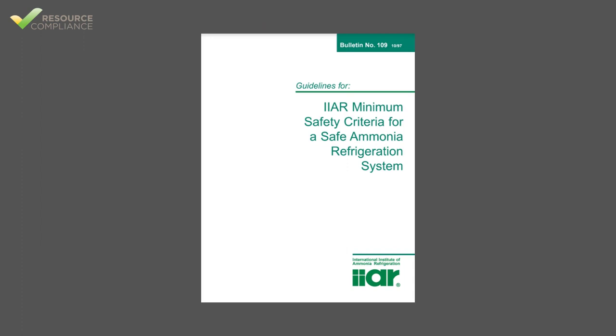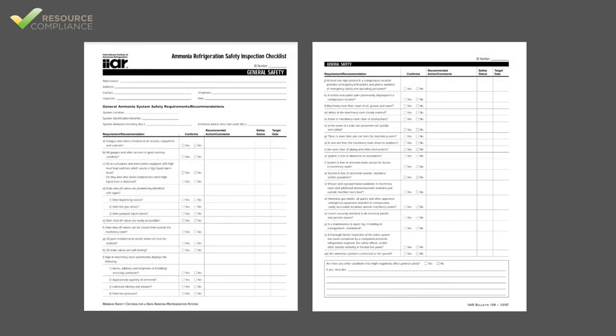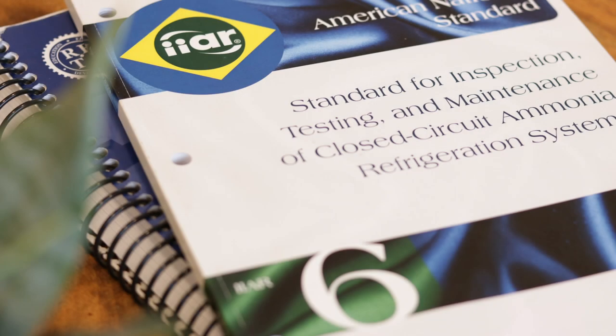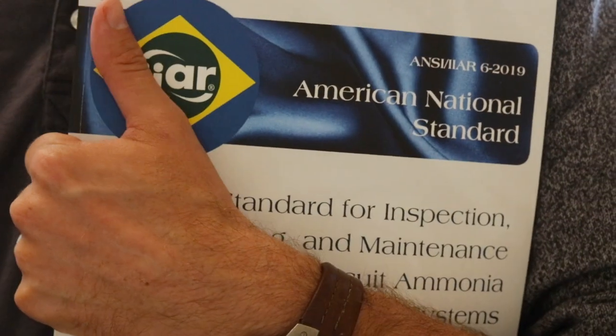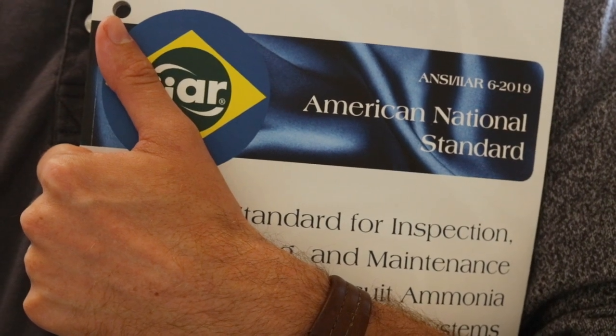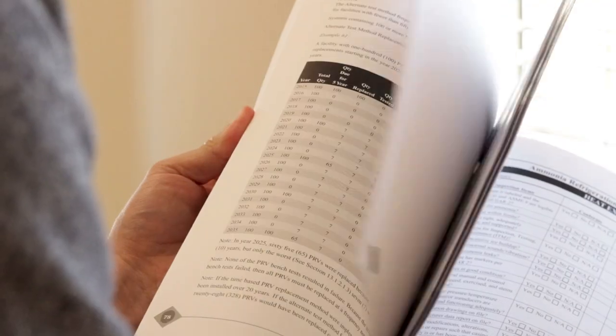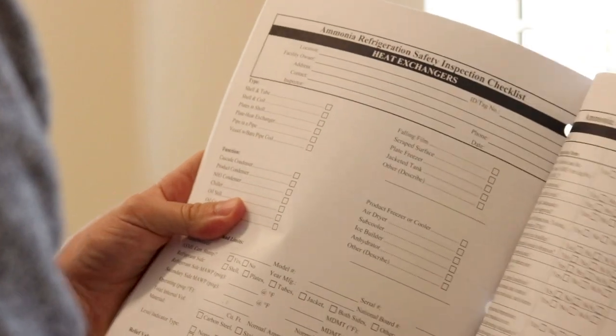For years, the Bulletin 109 checklists served as the gold standard for documenting annual mechanical integrity inspections for ammonia refrigeration equipment. In 2019, IIAR retired Bulletin 109 when the first edition of Standard 6 was published. Standard 6 addresses the minimum requirements for inspection, testing, and maintenance of ammonia refrigeration systems and includes slightly altered versions of the B109s in Appendix B.